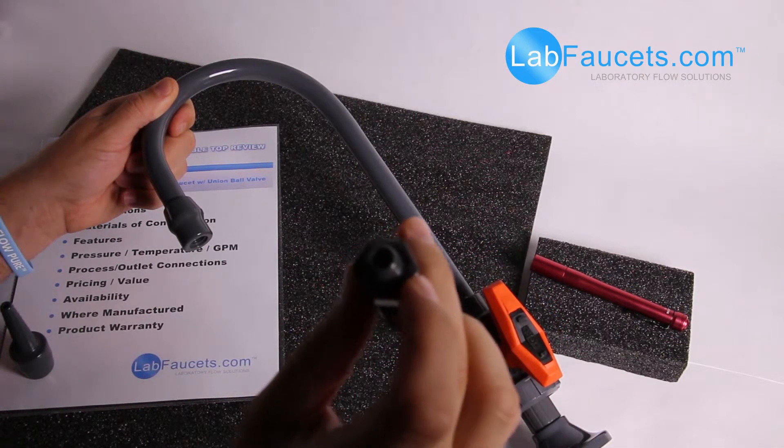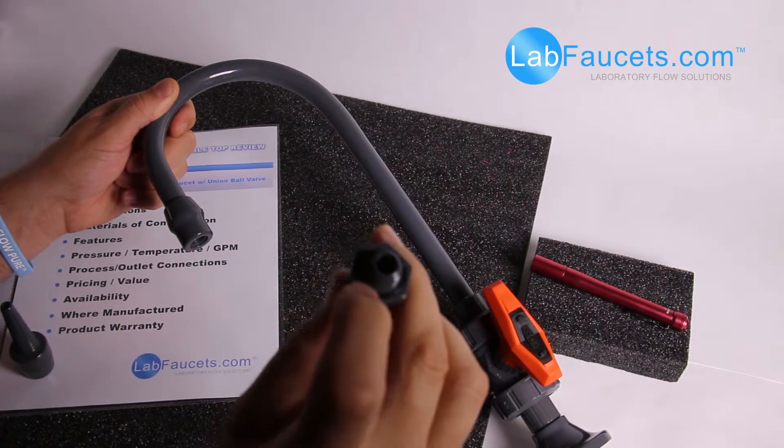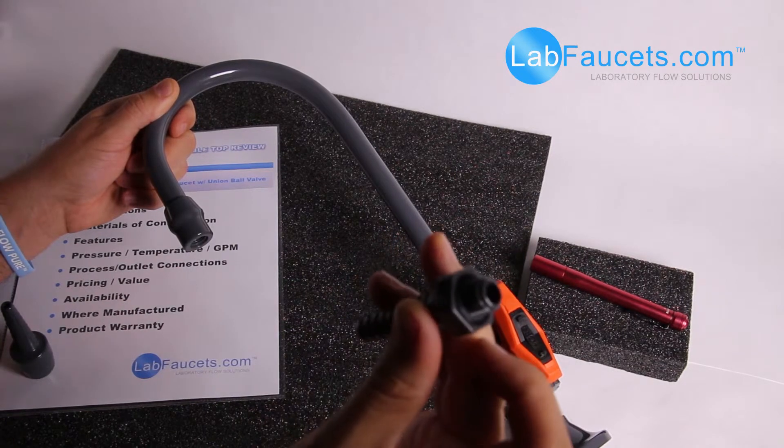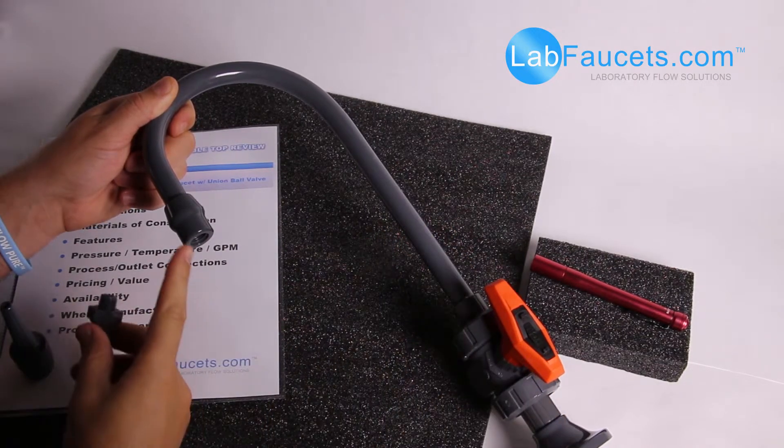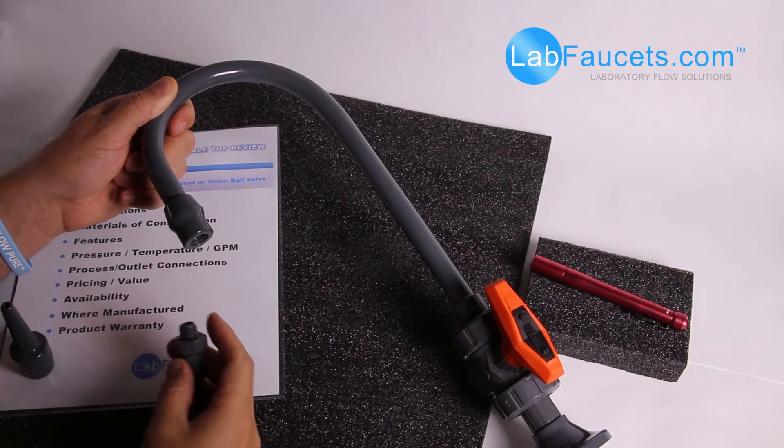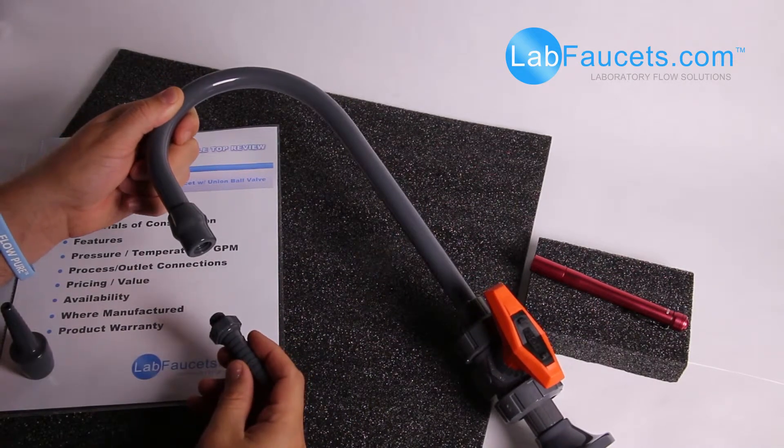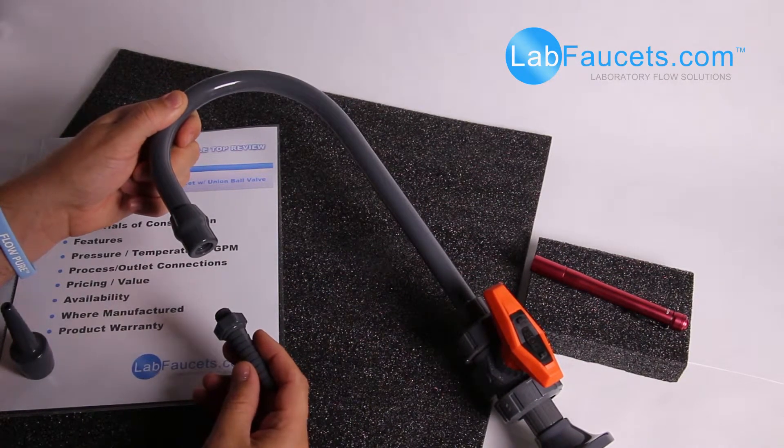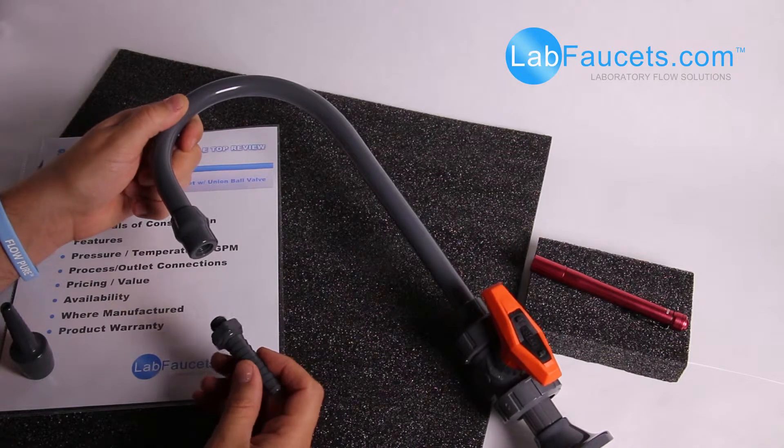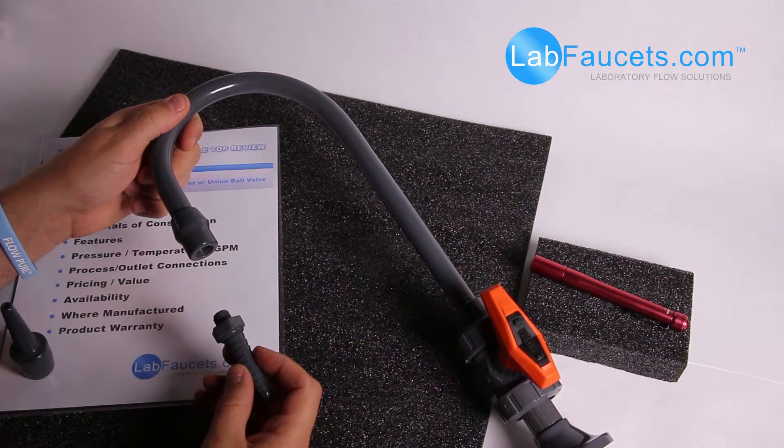It seals to the adapter fitting here with an O-ring, a Viton O-ring. And we've done studies and it provides a very legitimate sealing method.